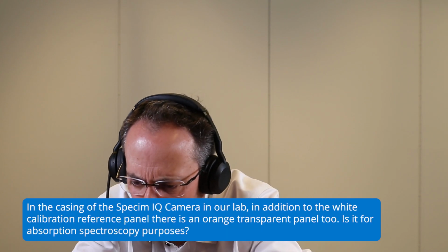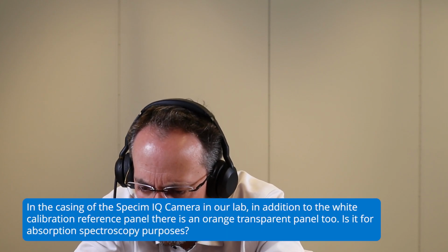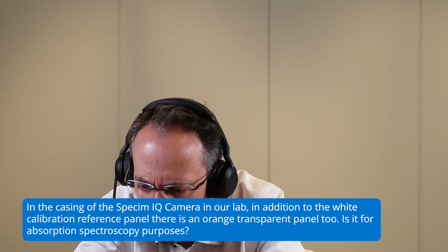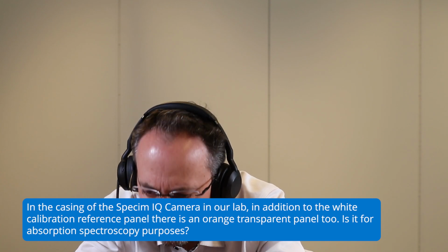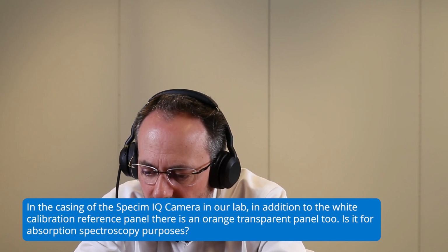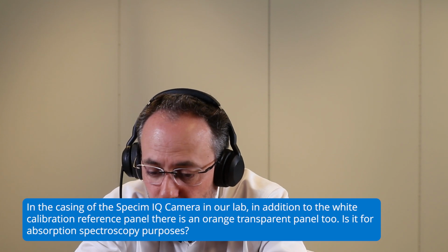In the casing of the Specim IQ camera in our lab, in addition to the white calibration reference panel, there is an orange transparent panel too. Is it for absorption spectroscopy purpose? No. It is here to check what is the spectral calibration of the Specim IQ. Every now and then, if I recall well, it's every 3 weeks, the IQ camera is actually asking you to check what is the spectral calibration. So here you just need to have the white reference.